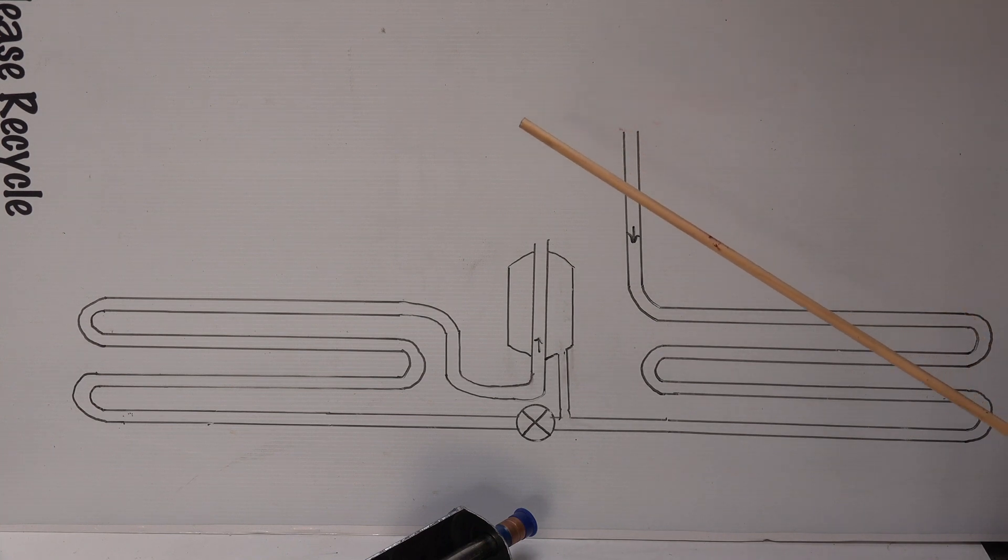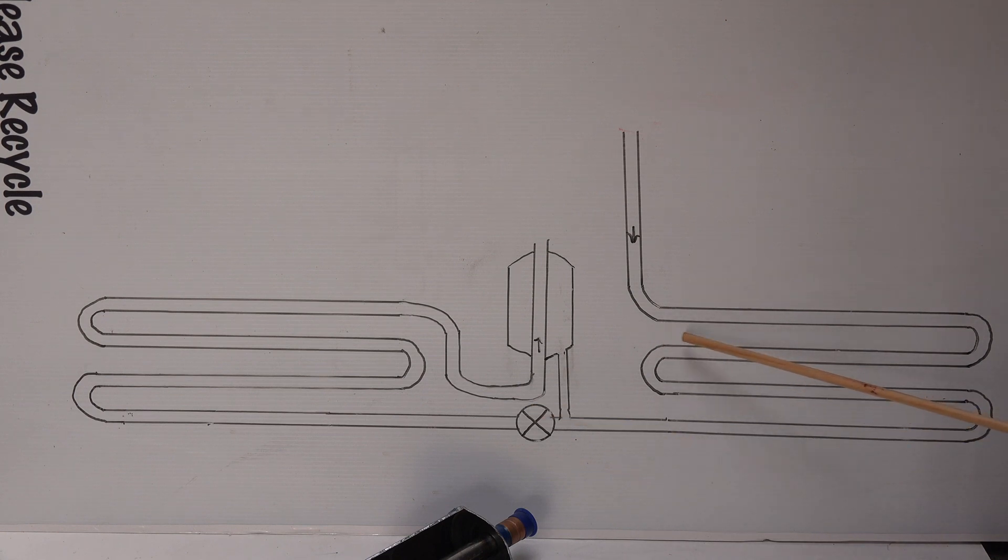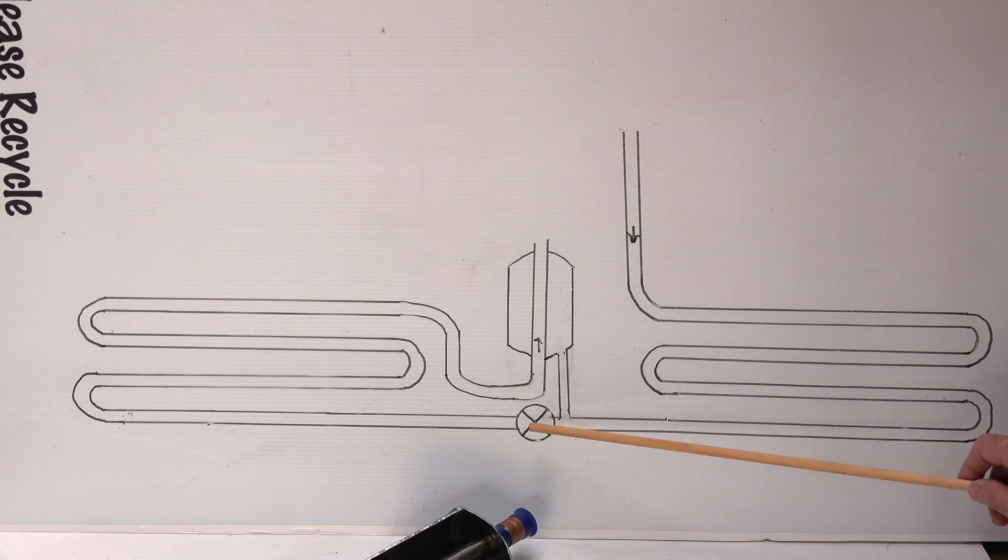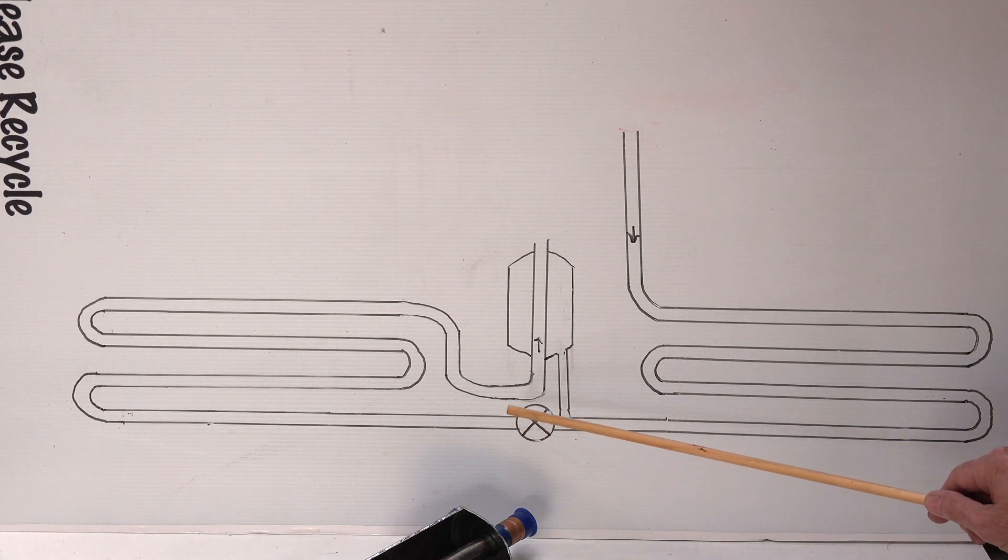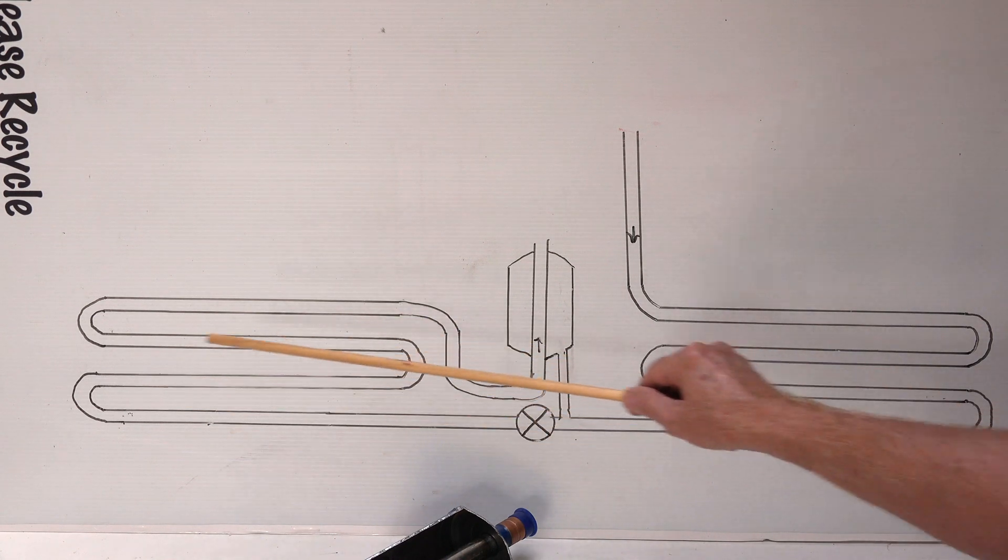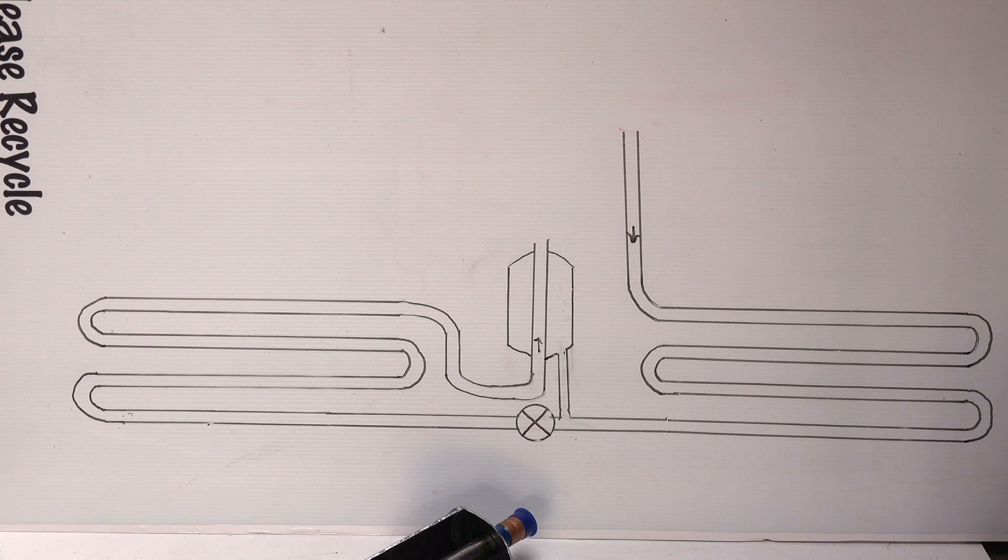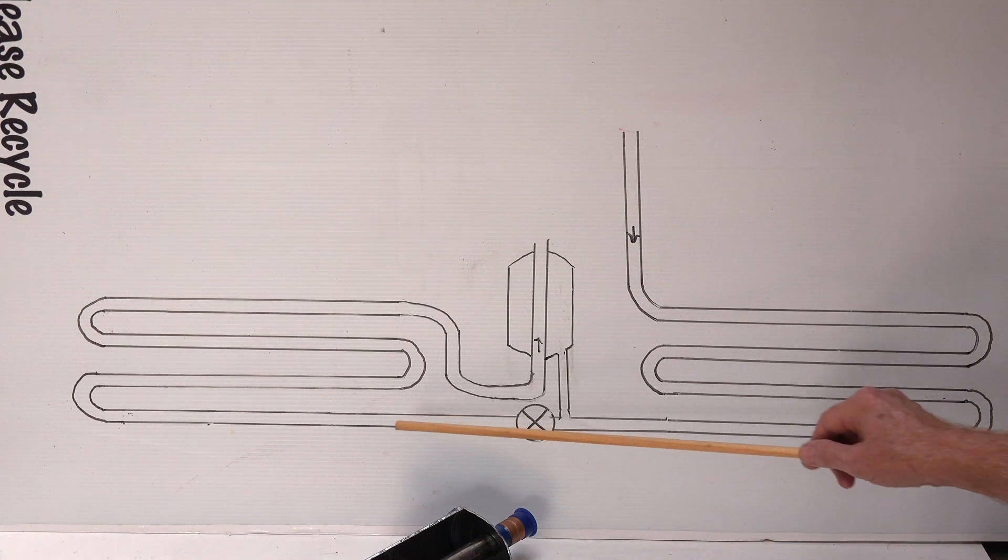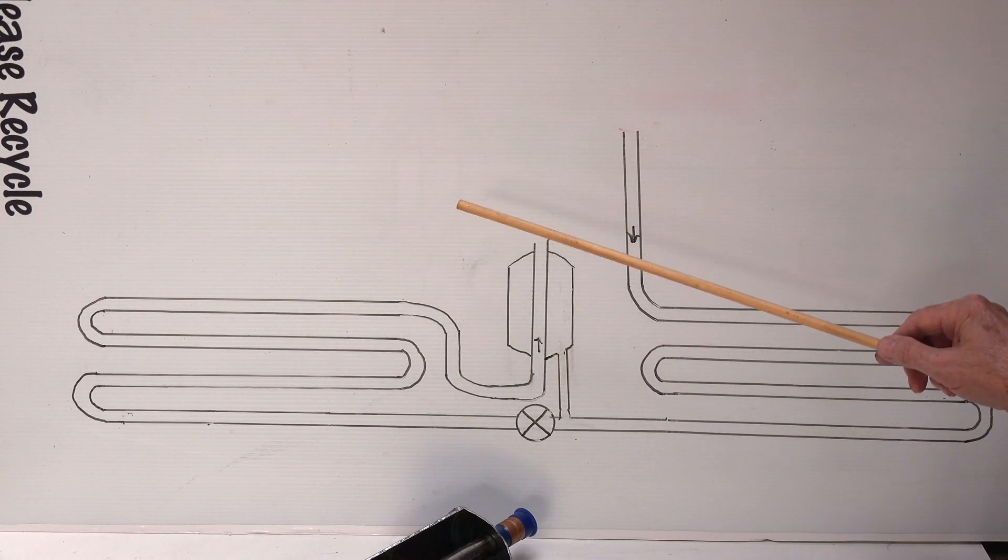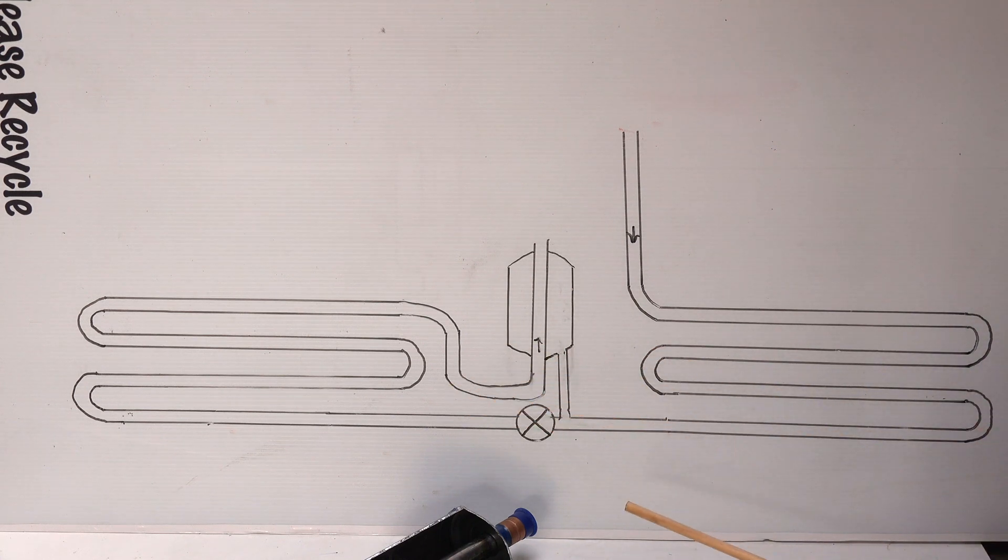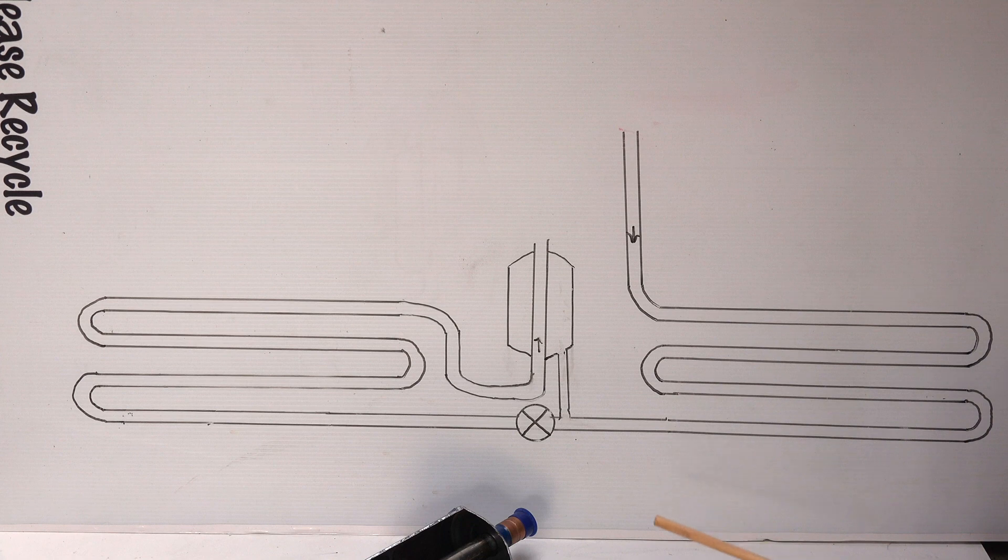So where does that refrigerant go? It goes out here into the condenser. Because we have a TXV, it is going to feed enough refrigerant into the evaporator to get a superheat that corresponds with what the expansion device wants. So it'll evaporate an amount of refrigerant depending on superheat that may be very low in cold outdoor temperatures.